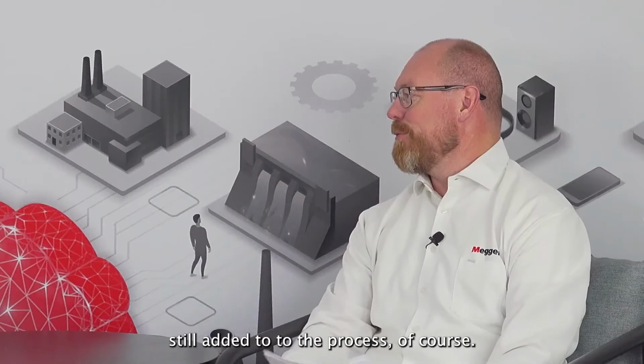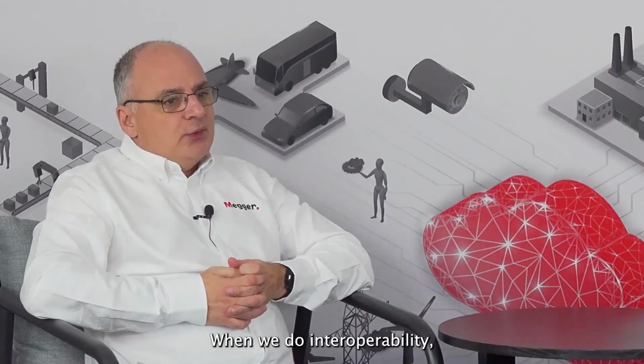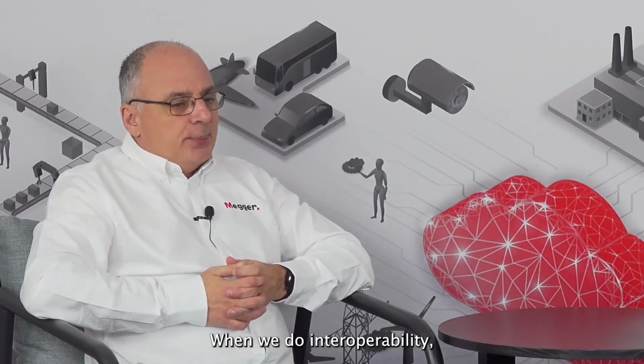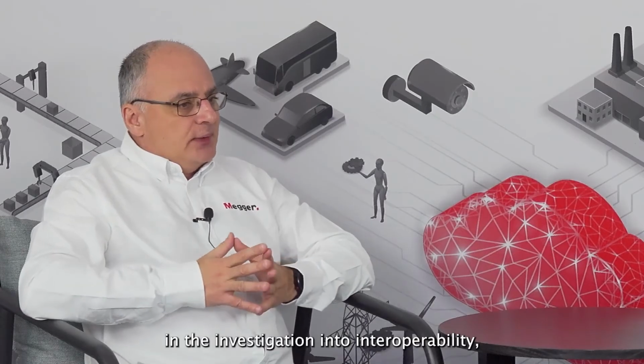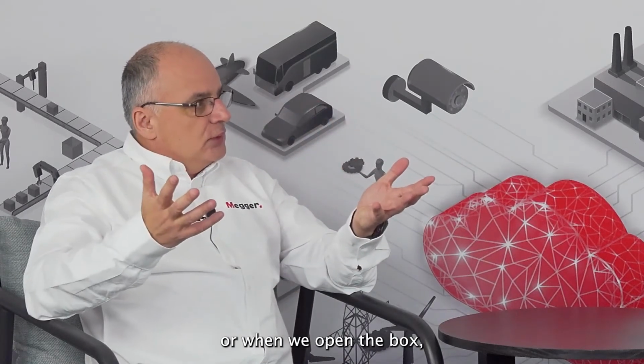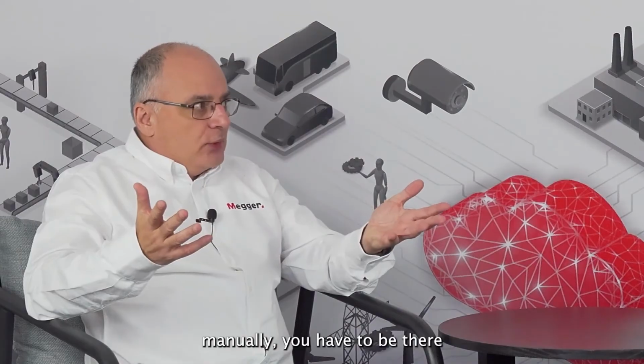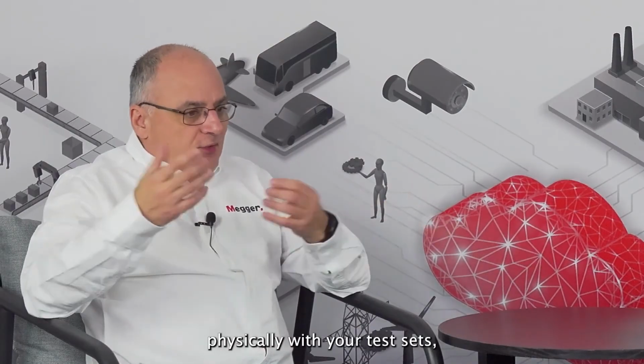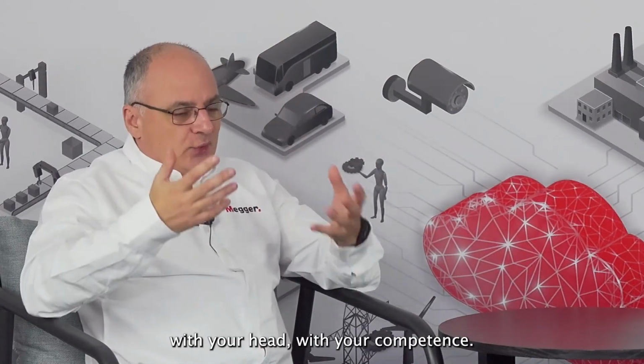You know that is the difference, and you have to find out how to fix it. The problem could be in the SCL, or the problem could be in the firmware of the relay that is sending the GOOSE. So some manual work and some intelligence still has to be added to the process, of course. When we do interoperability investigation, or when we open the box, you have to do it manually. You have to be there physically with your test sets, with your head, with your competence.